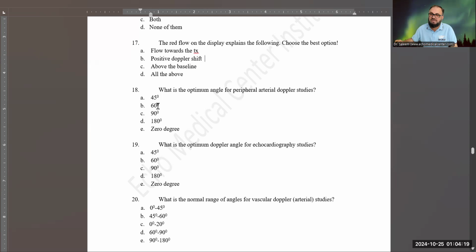Exactly. 60 degree. B is the correct answer. 60 degree is the optimum. Now the question is, why 60 degree? Because if you go below the 60, you're going to get a better Doppler shift, but then your transducer will not be able to penetrate the artery with the pulses. So it will bounce from the artery. It will not penetrate it. If you make your angulation close to 0, like coming to 30, 25, 20, something like coming to a smaller angle, that will be the problem.